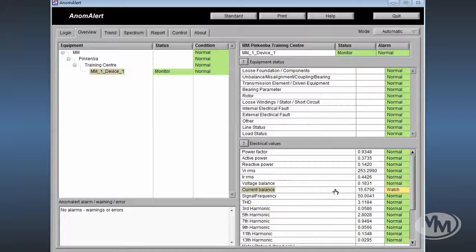Every 90 seconds, Anomalert calculates the parameters of the connected motor or generator and compares these values to its learnt model values. After some time, when statistical persistence criteria have been met, this watch warning will be elevated to an equipment status alarm and be flagged in the upper window.